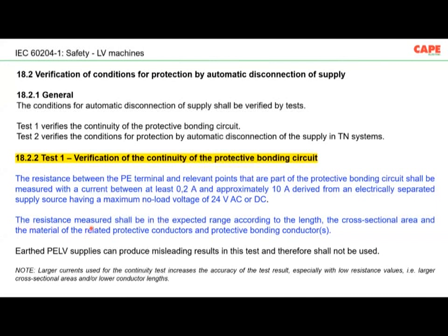Then the resistance measured shall be in the expected range according to the length, the cross-sectional area, and the material of the related protective conductor. So basically, imagine for a typical system you require 35 square millimeters of copper wire. After making the connection, you check the resistance of this particular wire, find out the resistance of the wire from the manufacturer's catalog or from the recommendation of the standard, and find out whether the resistance is within the limit. So what do we achieve here? Loose contacts are nullified. You are sure that there is no loose contact. The resistance of the wire is good, so that there is no cut in between.